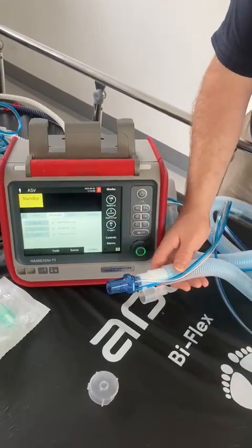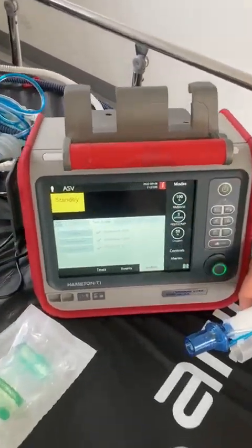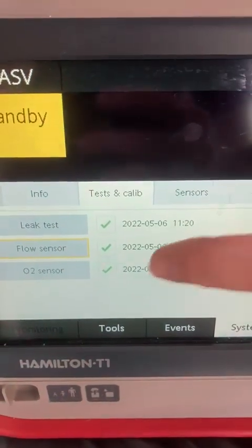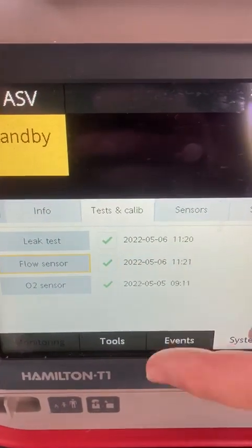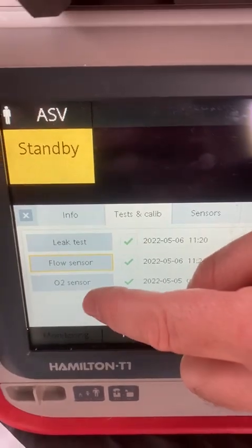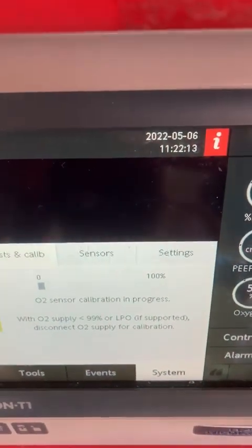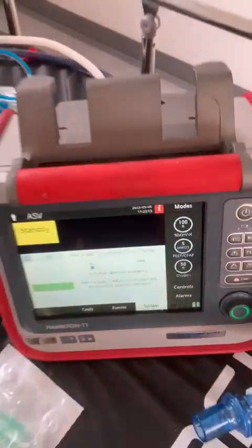And then the third one, if you have a green tick beside the O2 sensor, you don't need to calibrate it. If there's a red X here, you must do it, or you can do it if you want to. But to do it, all you do is press the button, and then we wait 2 minutes until this bar comes across to 100%. But that's all you do. Press the button and wait 2 minutes.